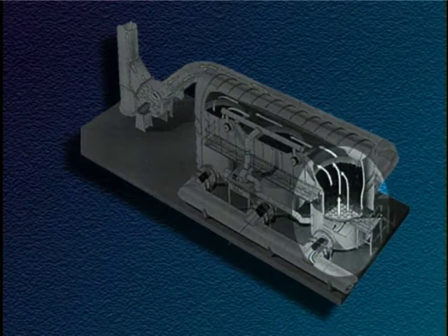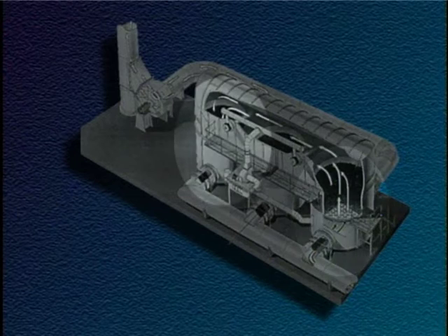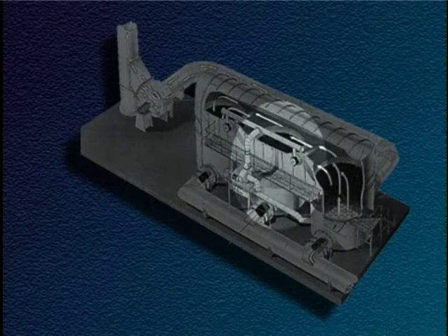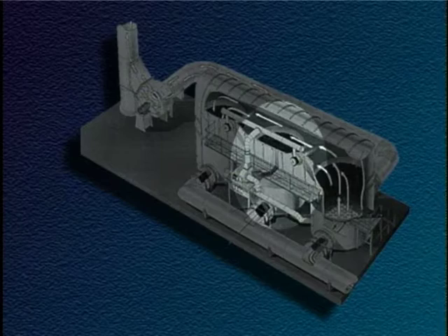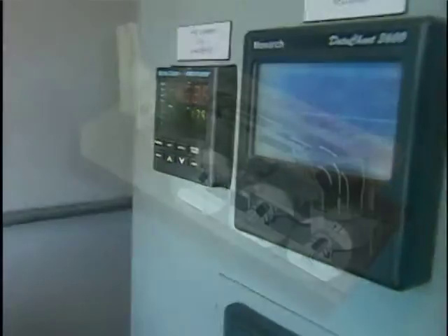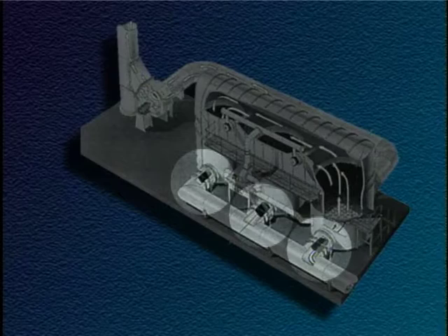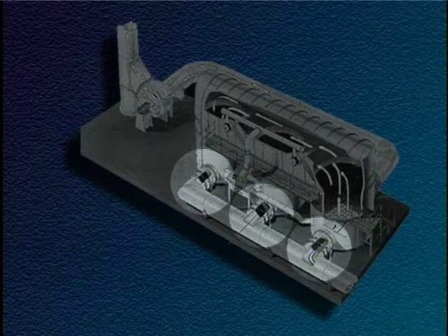One bed is used to preheat the waste gas stream. One bed is used to store heat from the treated gas stream. And one bed is in a purge cycle. The purge cycle is needed to prevent emission spikes each time the gas flow is reversed.